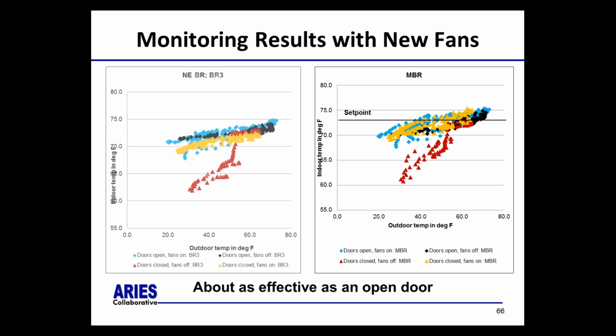The monitoring results with the new fans showed that they're basically equivalent to an open door. These plots show the indoor temperature on the left for each of 4 conditions. The left plot is a small bedroom, bedroom 3, and the right plot is the master bedroom. The set point is about 74 in these plots, and you can see that except for the red triangles, everything's pretty much clustered together, and those conditions are shown in the key below.